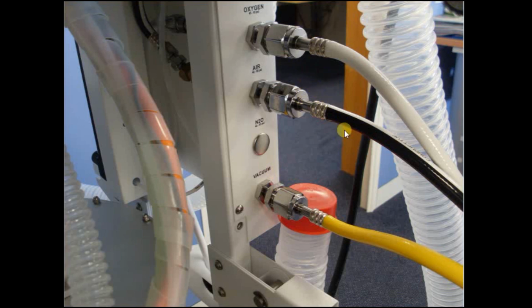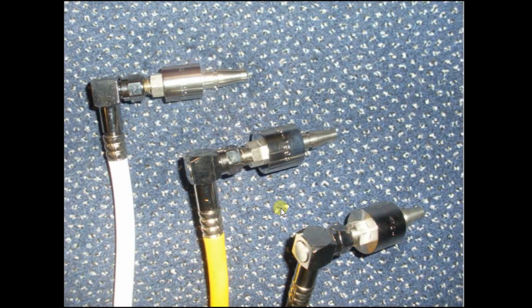This picture shows more clearly the connections for the hose fittings, which use NIST fittings, which are non-interchangeable screw threads. What that means is that you can't connect by mistake the oxygen hose to the air inlet and vice versa. On this machine there's no nitrous fitted, although there is an option for nitrous on any machine that you purchase. At the bottom we have the vacuum line taking air and gas away from the machine to a standard vacuum circuit. At the other end of the hoses we have, in this instance, the British BS probes that we will fit, but these probes can be replaced by any fitting peculiar to the country that it's being shipped to or being used in.